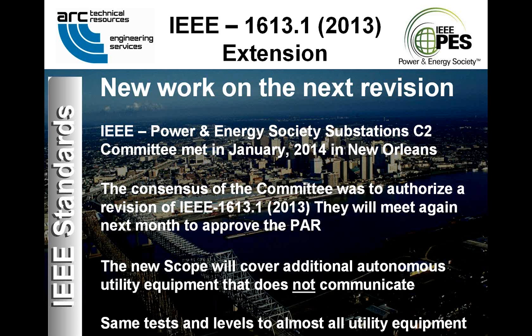The newly revised standard will apply the same tests and test levels to practically all utility equipment inside substations and out in distribution. We're still forming that working group, and work should begin later this year on that. Recently, going off my slide here, we just had a meeting of the Substations Committee, and they went over this again. The PAR is now approved, and the working group is forming. And we have 3 committees within the Power and Energy Society that are sponsoring new work on 1613.1 to expand its scope. It would be the Substations Committee, the sponsor, and the Power Systems Relaying Committee, and the T&D Committee, which is a co-sponsor.